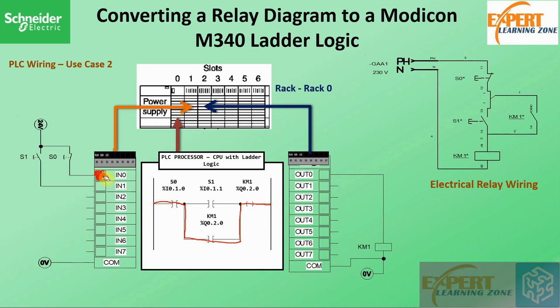Remember that this bit is active. If we want to terminate the system or put off the load, we need to cancel the logic present at that point by pressing S0. When we press S0, it becomes false here, this contact breaks open, and the coil also breaks open. Remember that this contact follows this coil — when the coil goes off, the hold-on contact opens and the system turns off.